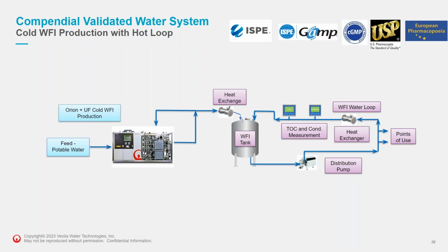In terms of energy, heating 1 litre of water from 15 to 85 degrees, on that 70 degree delta, takes just under 300 kilojoules. So 300 kilojoules against 2,700 kilojoules. Again, there is a clear saving in energy consumption and utility cost in running a hot WFI loop, even with a cold WFI membrane system generating to that system using a heat exchanger. There are clear advantages of doing it this way compared to a conventional distillation system.